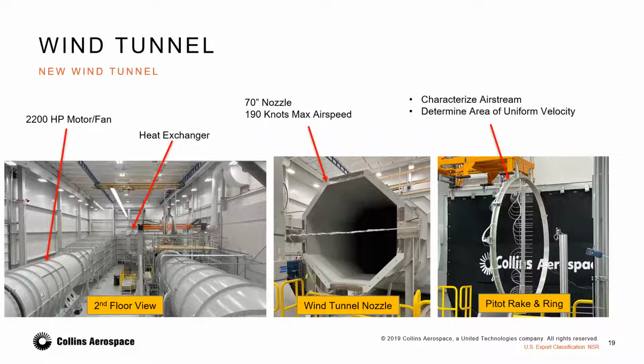There's a 2200 horsepower motor fan combination driven with a variable frequency drive. The VFD is actually what's controlling the airspeed with closed loop control on a differential pressure measurement in the contraction. So the differential pressure is what's telling us the airspeed, and we use that as feedback to the VFD to be able to control our airspeed to the RAT.